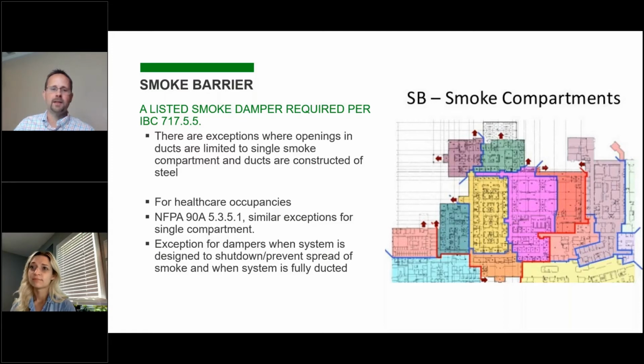And that's another thing to clarify, because there is a place you would have a fire smoke barrier where it needs to have a fire resistance and a smoke resistance, but it's different from something that's separating 2 smoke compartments. So it's important to clarify if you see that on a plan and it looks like it's a true smoke barrier as Glynis described, but it has other verbiage on it. So the exceptions where you don't have to put a smoke damper, there aren't tons of them in this one, but the main thing is if you only have air outlets or inlets on one side of the smoke barrier, you can omit smoke dampers.